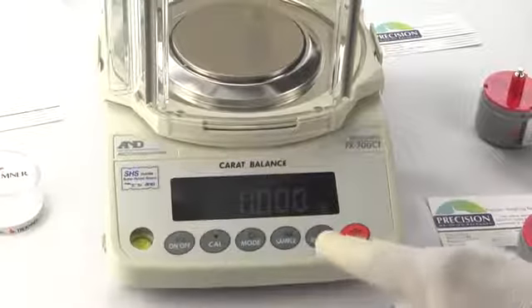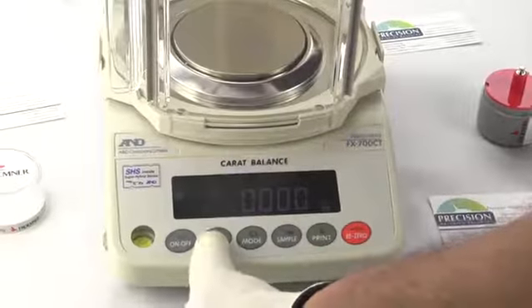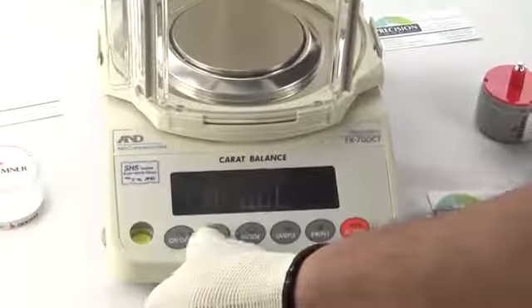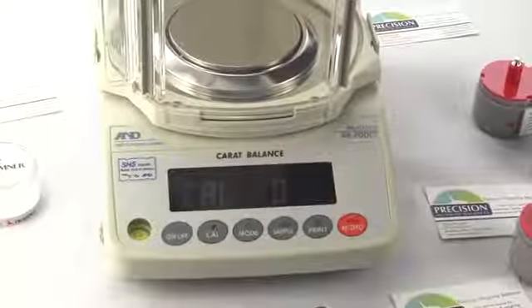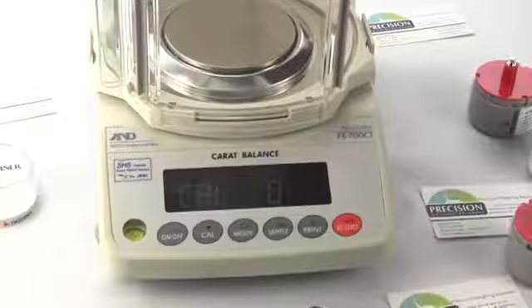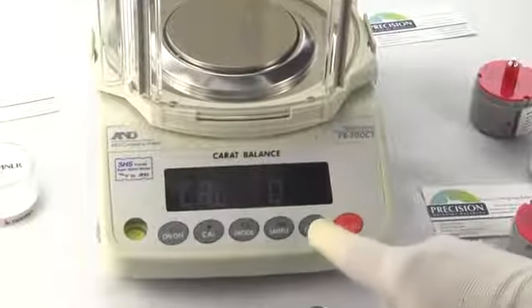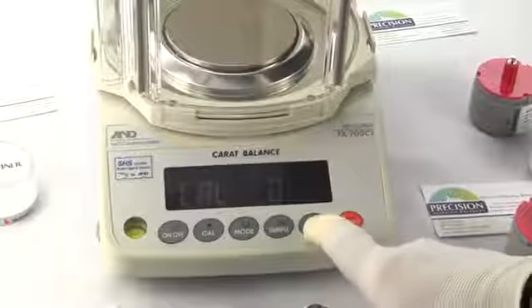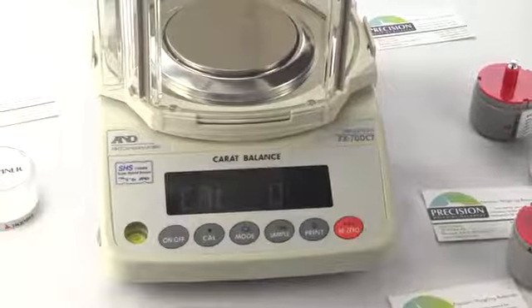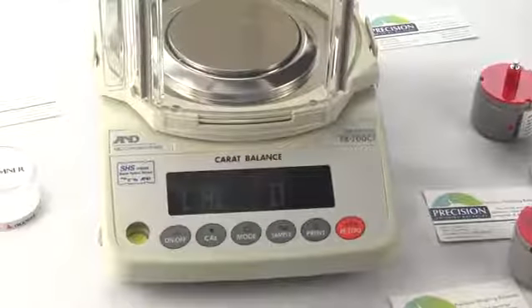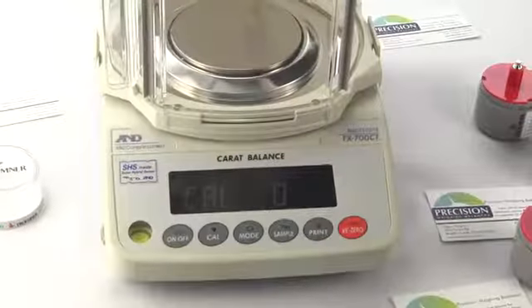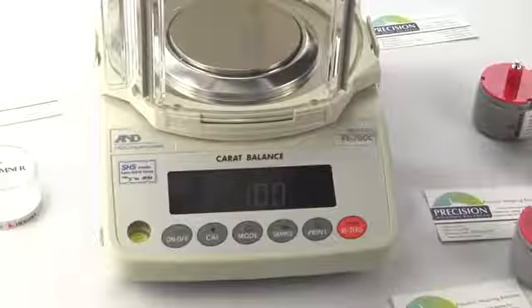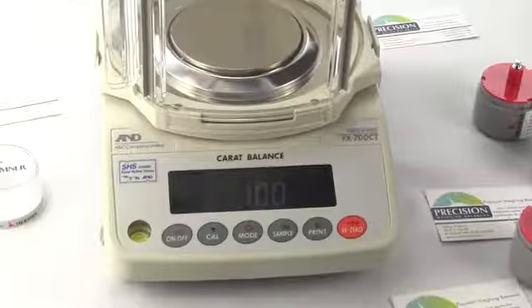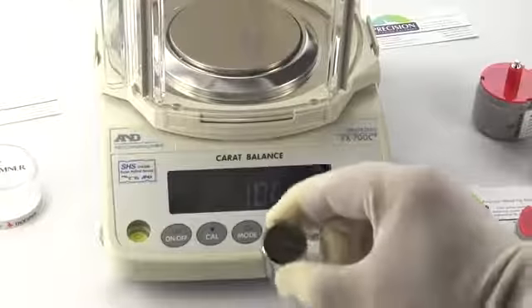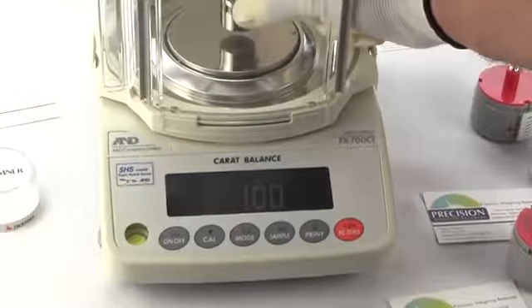And so what one does to start a calibration is they press and hold the CAL key, and the balance says CAL OUT, and then it goes to CAL 0. And so at this point we want to press the PRINT key, and when we press the PRINT key, in the upper left hand corner there's an arrow there that's storing the 0 reference voltage. Now the balance shows 100. So we'll place our 100 gram weight on the center of the platform.